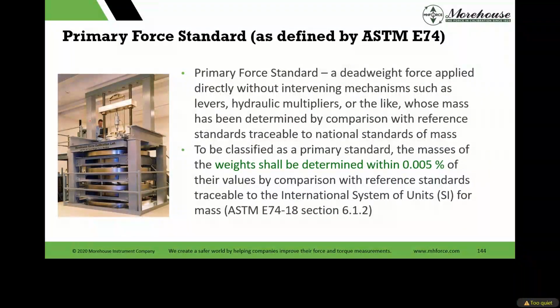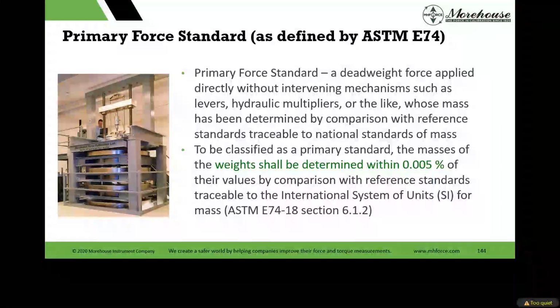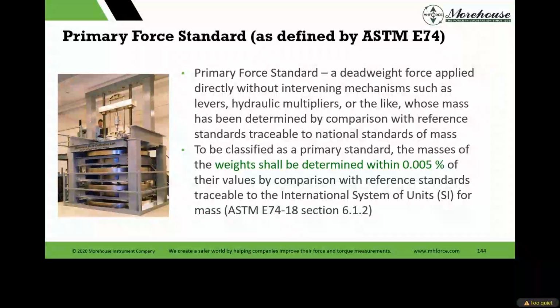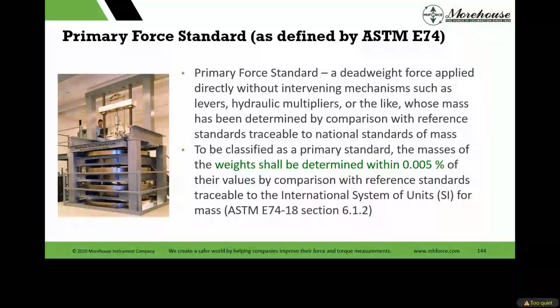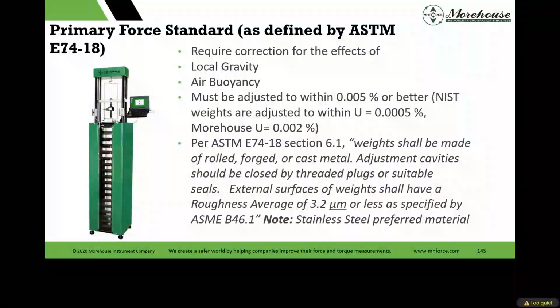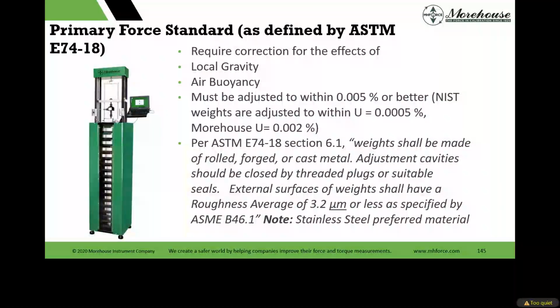It's basically mass, right? We're giving some target mass that we know is going to generate a force, because we're correcting for air density, material density, and gravity. And to be classified as primary, they need to be determined within 50 parts per million, and that's in section 6.1.2. And then if we're going to make a force machine, we want to know where you live, where you're going to make the measurements, more specifically.